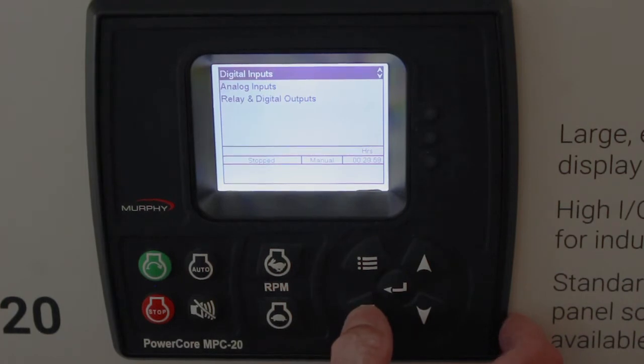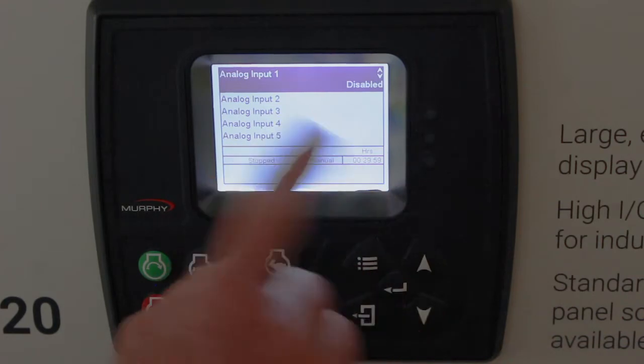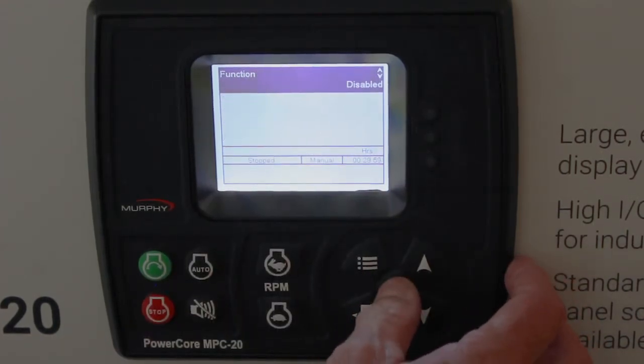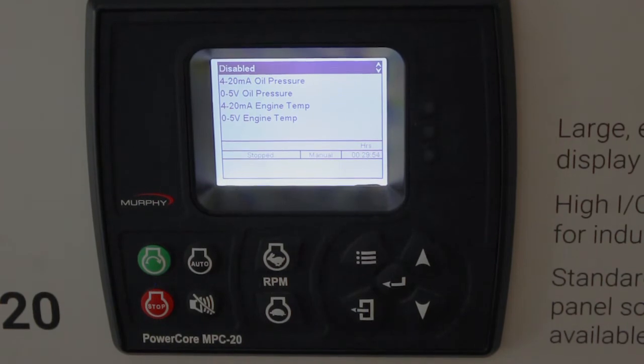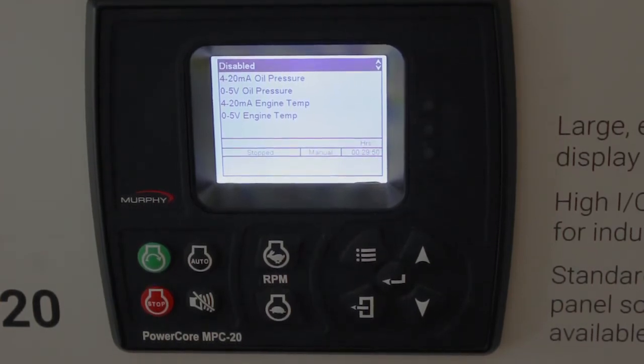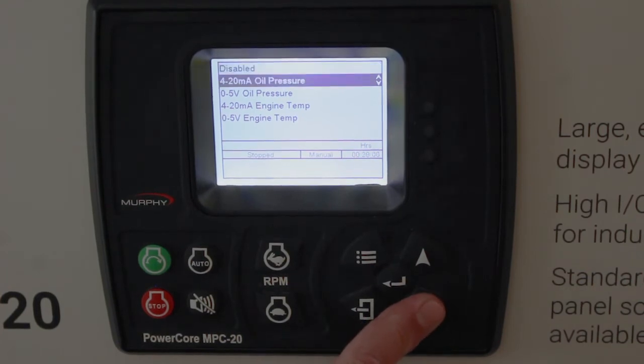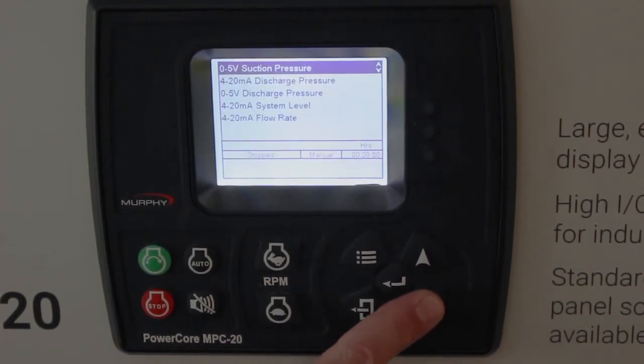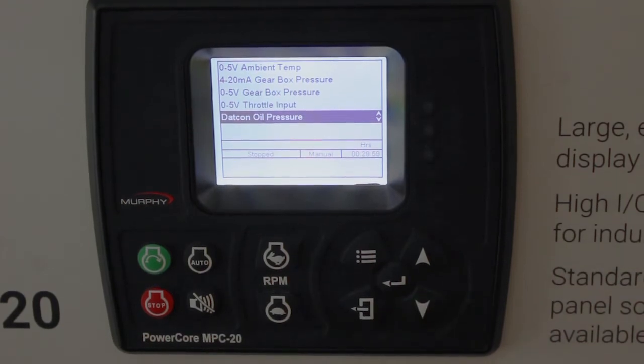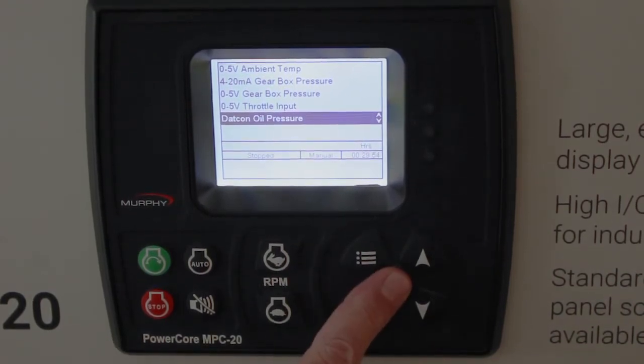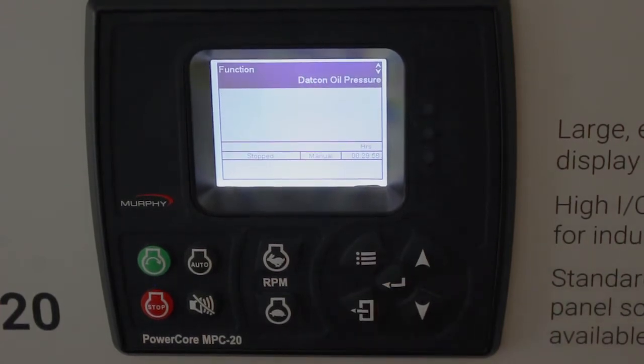Let's back up with the back button and go to analog inputs. Analog input one is disabled. Go to the menu and we have quite a choice. There's a difference between a resistive sender input and a zero-to-five or four-to-20 milliamp input. For instance, if you choose a Datcon oil pressure sender for analog input one, you're done — because we know what the lookup table is for the Datcon oil pressure, just like we do for the Murphy or the VDO.